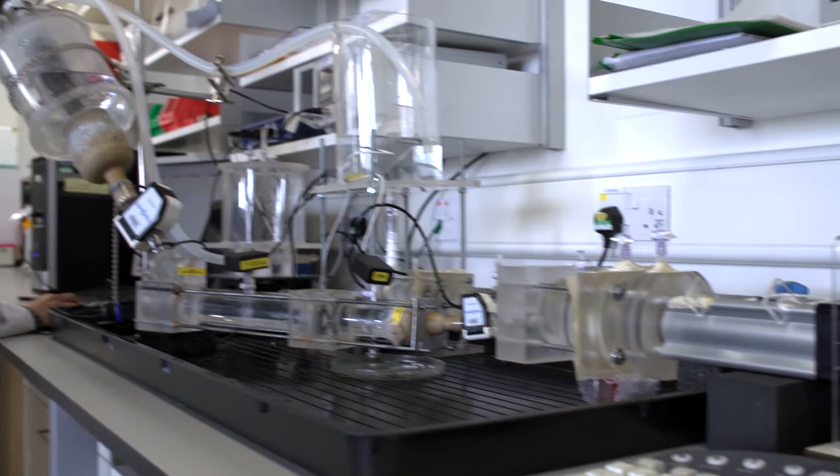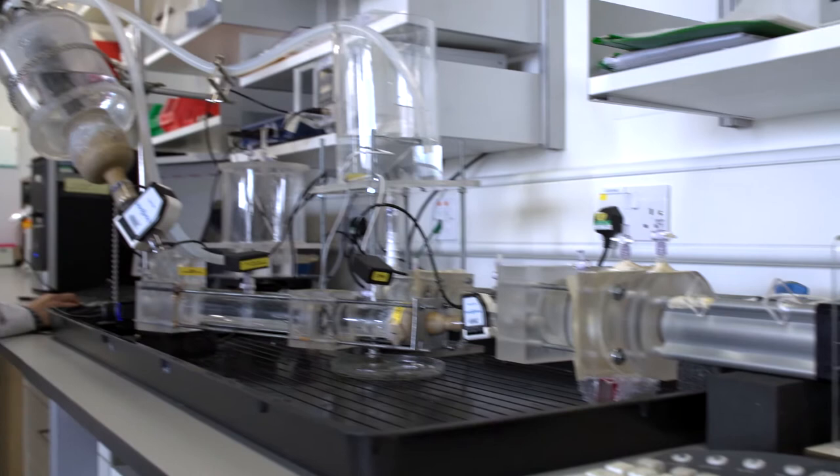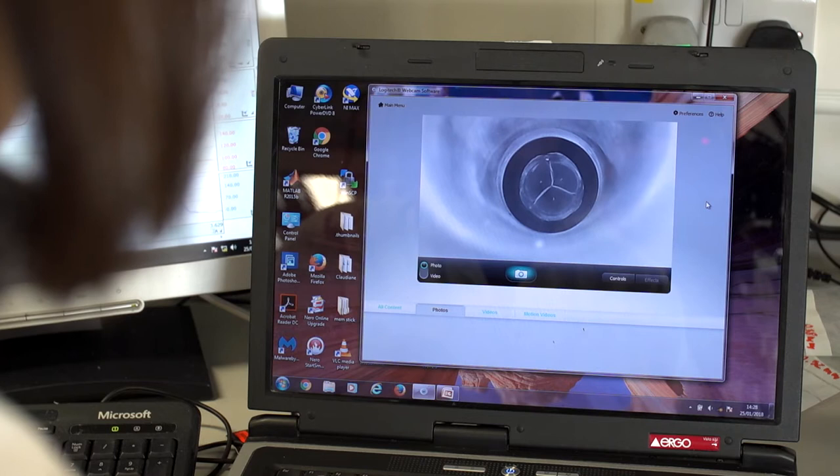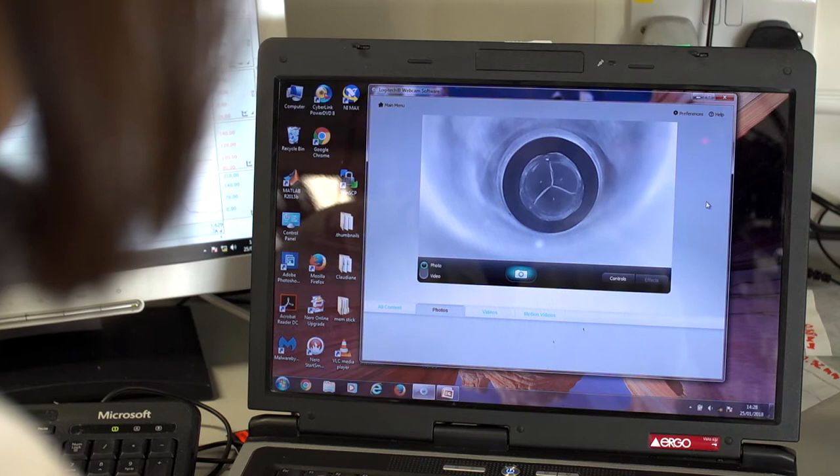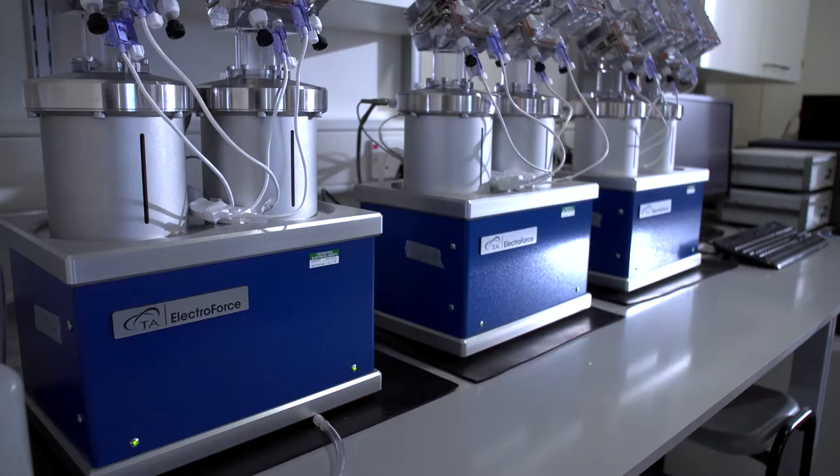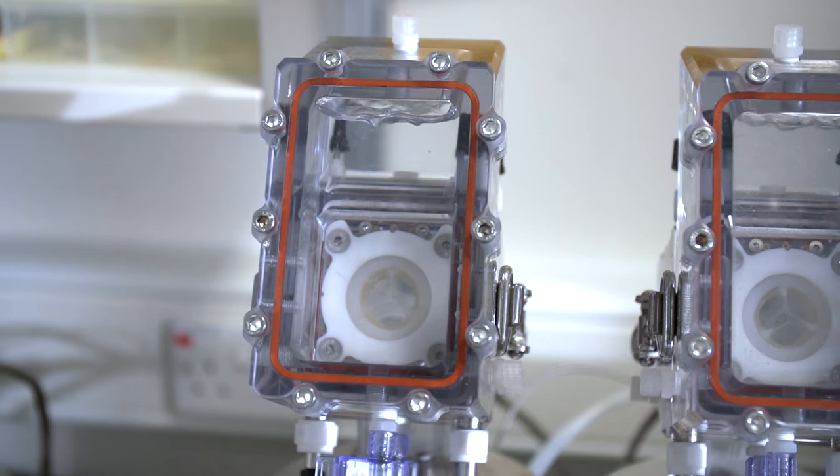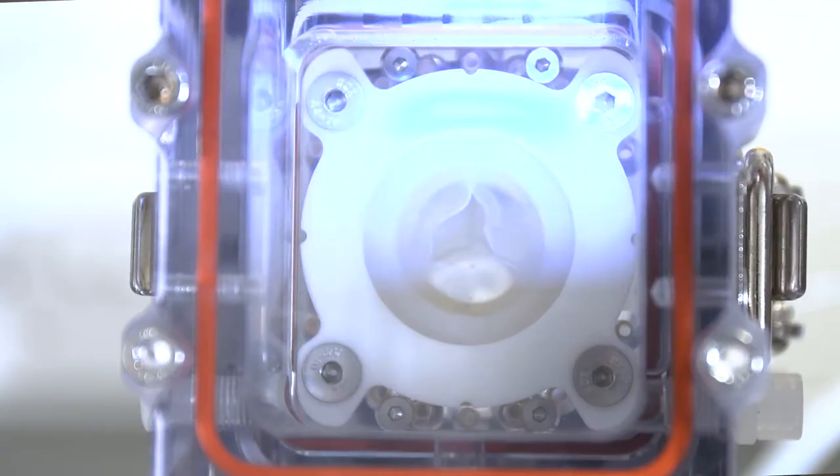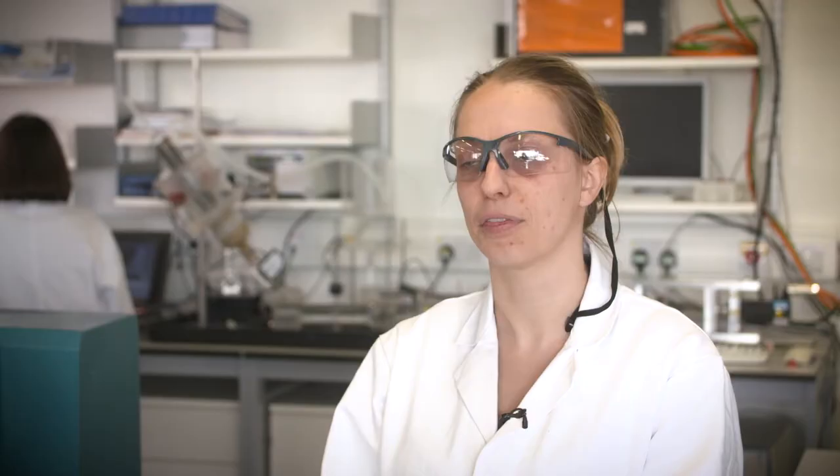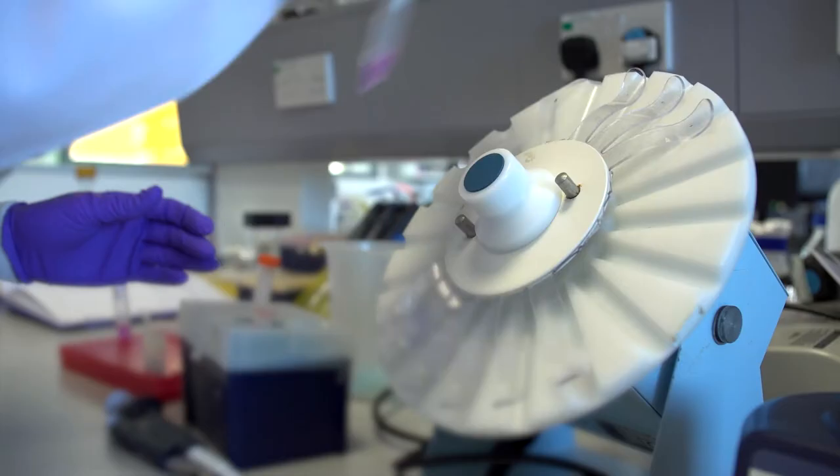So how we test the valve is we use firstly hydrodynamic testing in a pulse duplicator and then we can see how it performs in terms of how much it opens and how well it closes. Once we know that we're happy with the hydrodynamic performance, we need to see how long the valve actually lasts. We do that in an accelerated test called a fatigue tester where we rapidly open and close at a high frequency and measure the performance and count the number of cycles that it has performed.